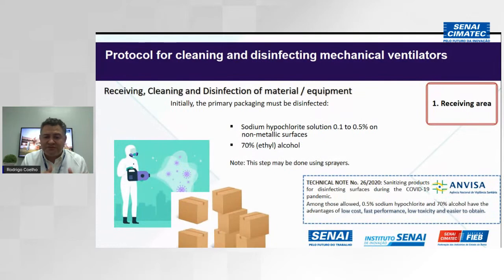So going to the first step, where we receive. The boxes arrive at our institute with the whole documentation, where I can check where this equipment belongs, when it was tested, and when it was last maintained, checking all the points of defects, and checking whether special attention must be given to some specific part of the equipment. Those documents are extremely necessary, and you cannot do anything without them. So the first thing is to check the documents that come with this material.